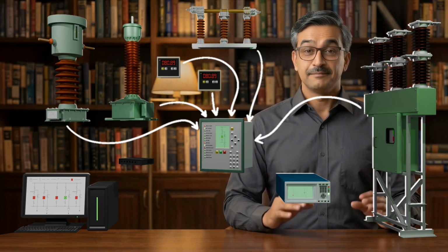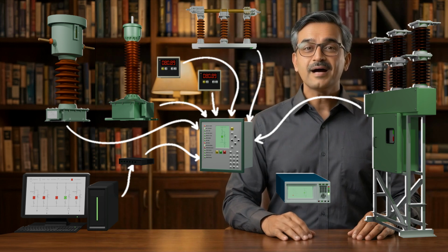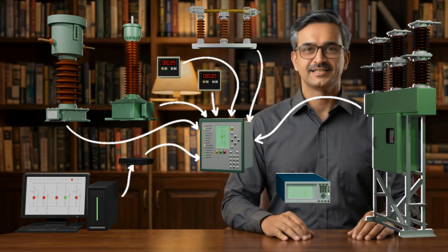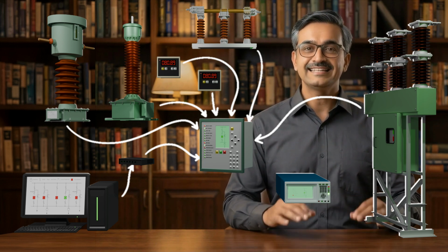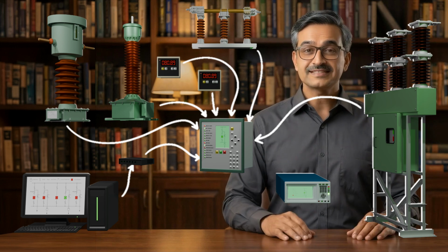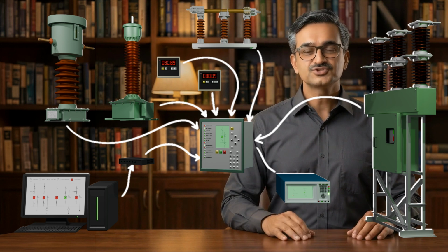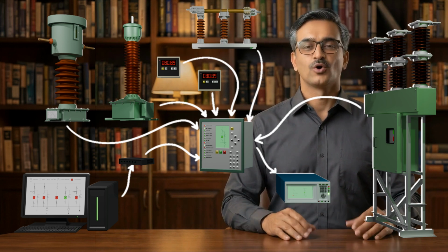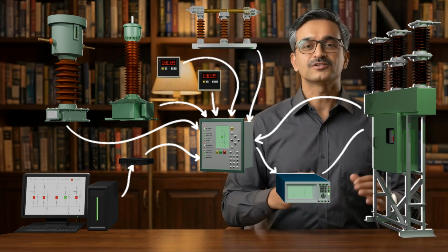Not only that, the BCU can also receive inputs from SCADA through its communication ports. So, if any command is initiated from the human-machine interface, or HMI, of the substation, the command comes to the BCU through the station bus and Ethernet switch. The central processing unit of the BCU processes that command and sends instructions to the intelligent electronic device, or IED, of the associated equipment like a circuit breaker or transformer.